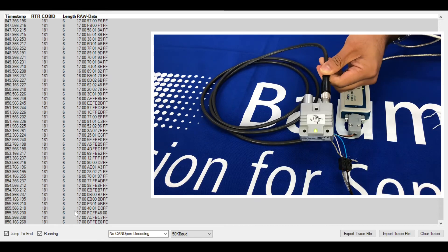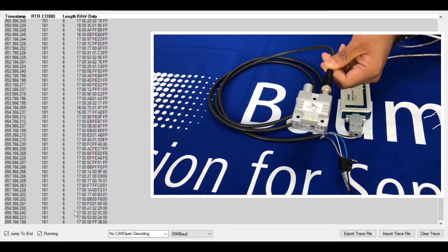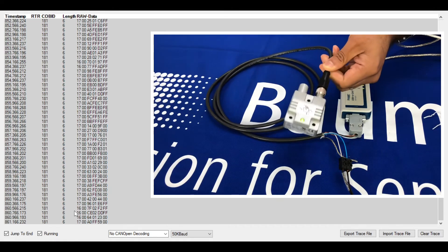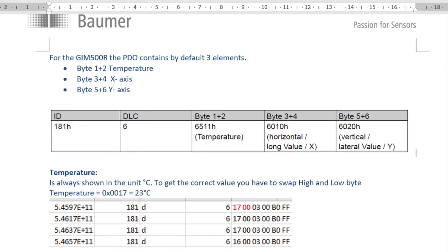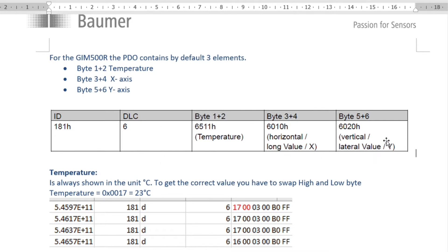Now that we're getting the hexadecimal output from the GIM500 inclination sensor, you saw the information coming out in that format. The actual data has three default elements: the temperature, the X-axis movement, and the Y-axis movement. The data was output with the timestamp, the COB-ID, the data length, and then the bytes information from the string coming out of the sensor.